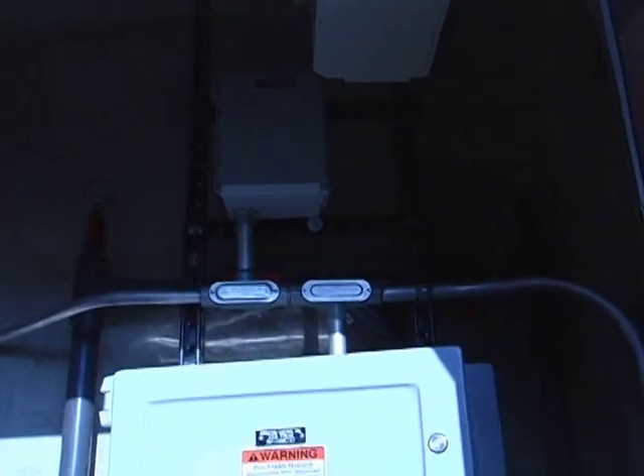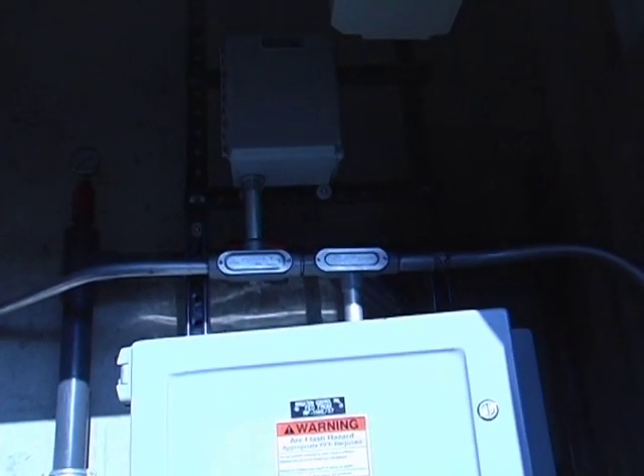So, once that water is heated, it passes up. You can see that there's a Y strainer in line there, and what that does is it protects the humidification chamber nozzles from clogging. So any debris that might be down in your recirculation sump well that's getting recirculated back up through the line, that Y strainer will catch that debris and filter it out so it doesn't foul your nozzles. And you'll be able to monitor the pressure drop through that Y strainer by those pressure gauges on either side. So you'll be able to tell from those whether or not your Y strainer is starting to clog up and if you need to pull it out and clean it.